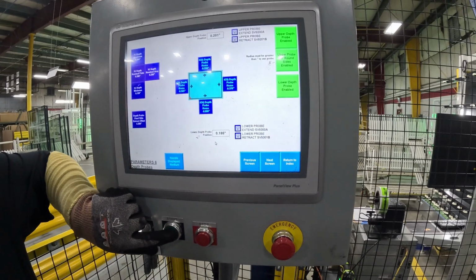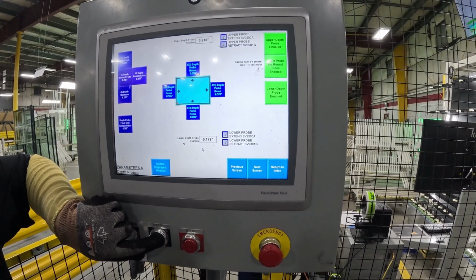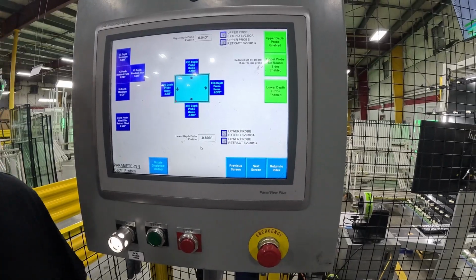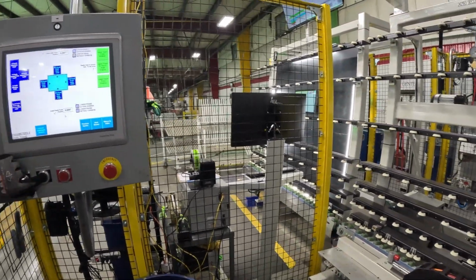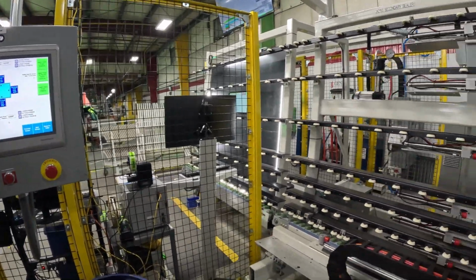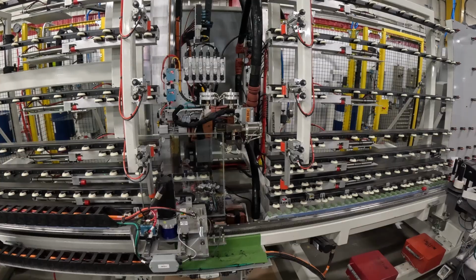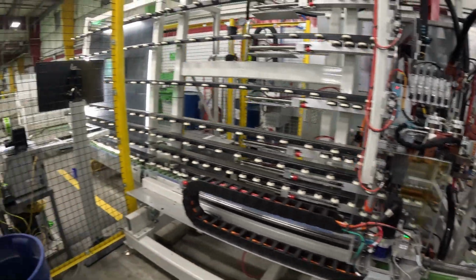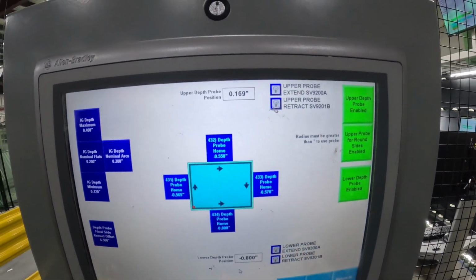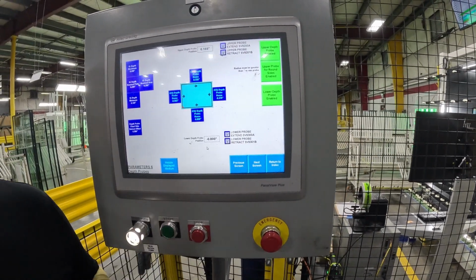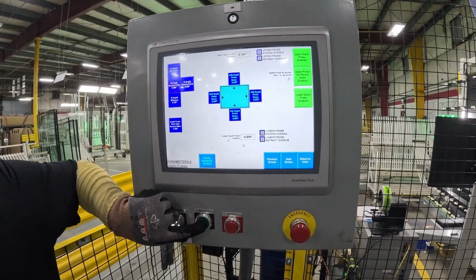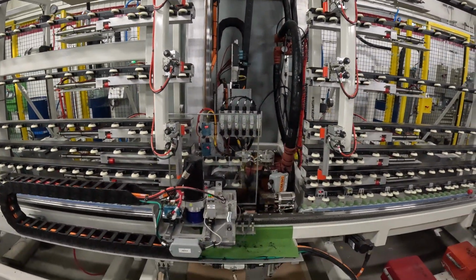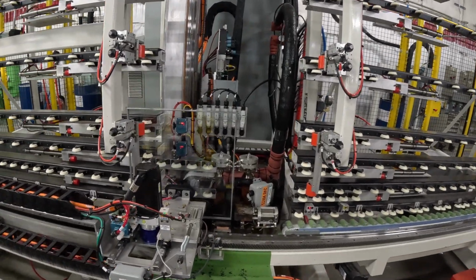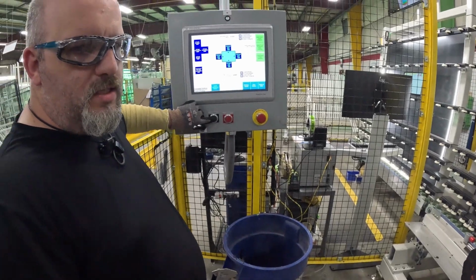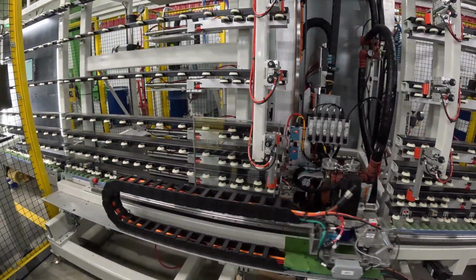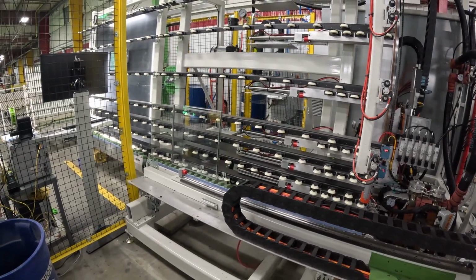So now just watch it as it trends across on top and bottom. We're pretty good there. Then you go to the trailing side. We're reading 168. On our unit, we wrote 165, so we're actually really good there, so we don't need to adjust that one. And it'll run down and we watch it. Now at this point, I can hit start a bunch of times, and then I'll just hit stop here.